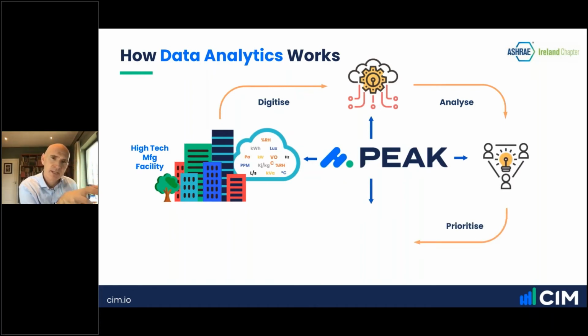What in CIM's case happens next is that we have a team of technical HVAC engineers, and what they do is they review and prioritize the issues that the software is identifying, because the software is intelligent, but it's not intelligent enough to prioritize the key tasks to go after. So there's a key piece of feedback we get from sites around BMS alarms: they are becoming a nuisance every day, because the facility technicians are getting hit with a tsunami of alarms that they just tend to ignore because they can't get to them, right? So what the human interaction is doing is helping prioritize and triage the issues that the software identifies.